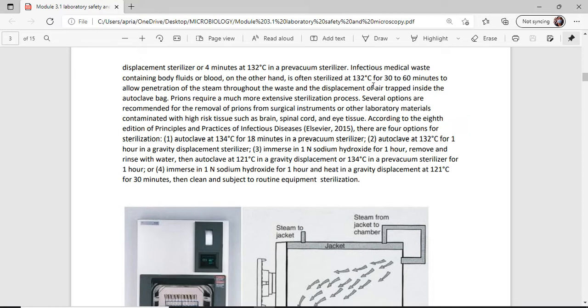Drill. Infectious waste containing body fluids and blood, on the other hand, is often sterilized at 132 degrees Celsius for 30 to 60 minutes and allow penetration of the steam through the waste and displacement of the air trapped inside the bag. That's why this is used for disposing of our body fluids, class. Because your body fluids, like blood, there's a lot of it, so you want the steam to penetrate to kill the microorganisms right away. So you need a longer period of time to ensure that it gets sterilized too. Next is...